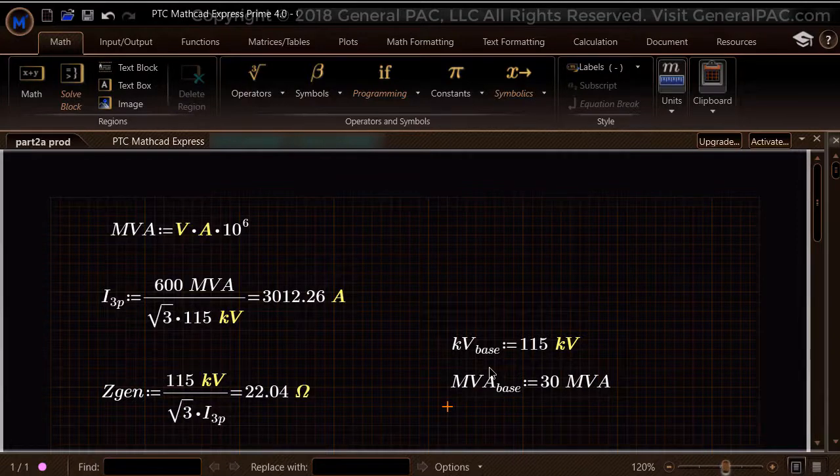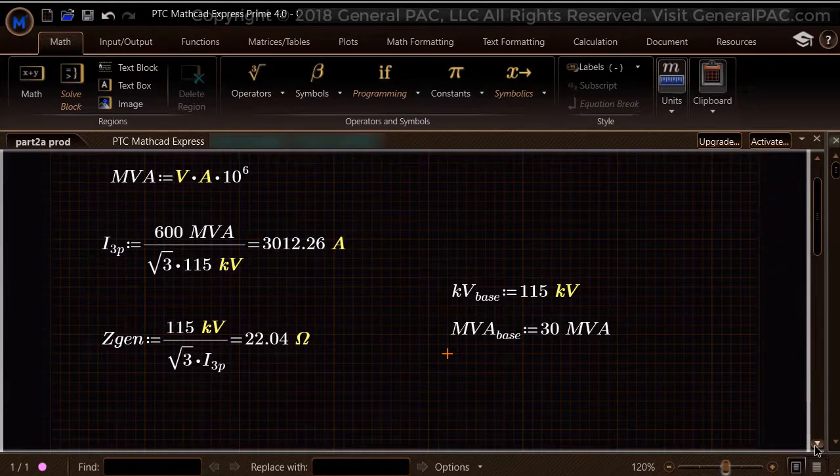This strategy will be explained when we calculate the transformer impedance. Please also note, in many books, articles, and modeling software, the power base is almost always selected as 100 MVA. But we have selected 30 MVA for our power base.